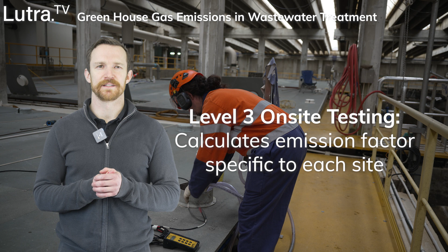Level 1, the least accurate method, uses a population-based approach to estimate standard loads for a wastewater treatment plant. Level 2 estimates emissions using specific plant operating data, including sample data and SCADA data. And Level 3, the most accurate method, uses extensive on-site testing to calculate an emissions factor specific to each site. For New Zealand, Level 2 is the most suitable approach, and most councils should strive for this level of analysis.